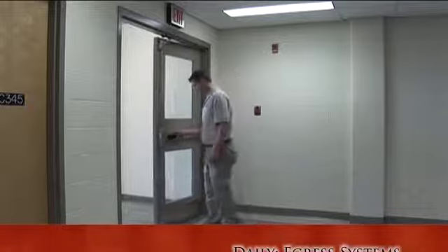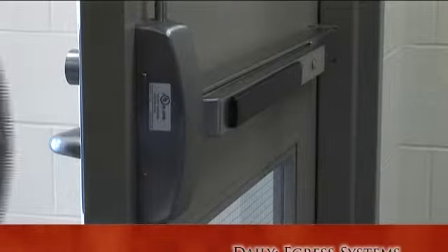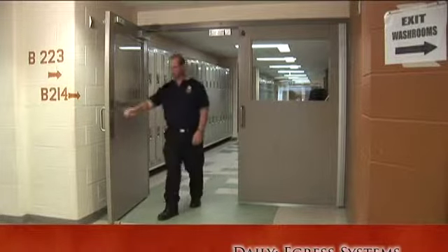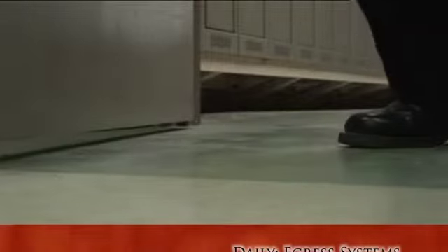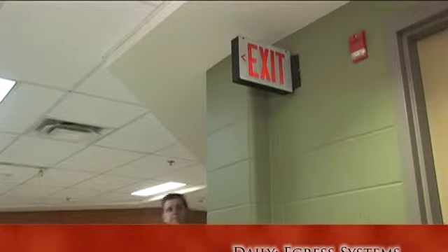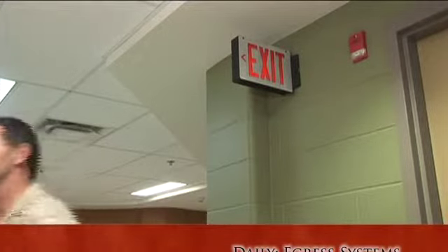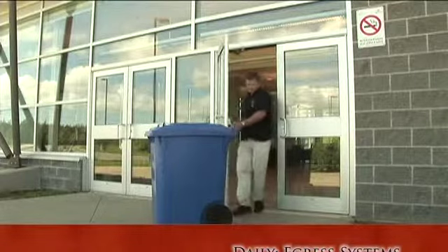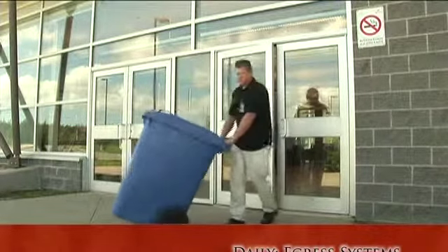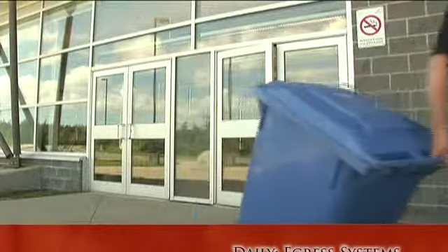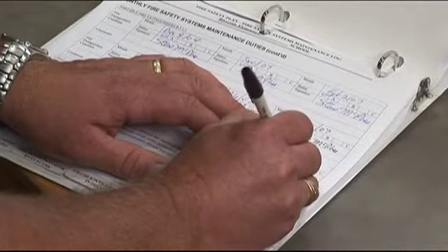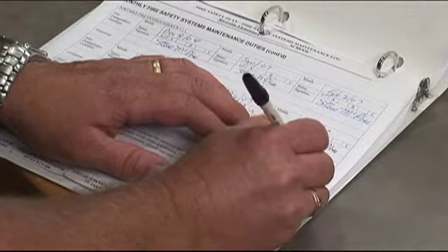Inspect doors and fire separations to ensure that they remain closed and latched unless the door is equipped with an approved hold-open device. Fire doors should not be held open unless they have an approved device. Exit lights and exit signs must be inspected throughout the school to make sure they're illuminated at all times. Also, inspect exterior exit paths to make sure that they're completely free of snow, ice, or other obstacles. Although these inspections are to be done on a daily basis, they only need to be checked off the appropriate charts in the fire safety system's maintenance log on a weekly basis.